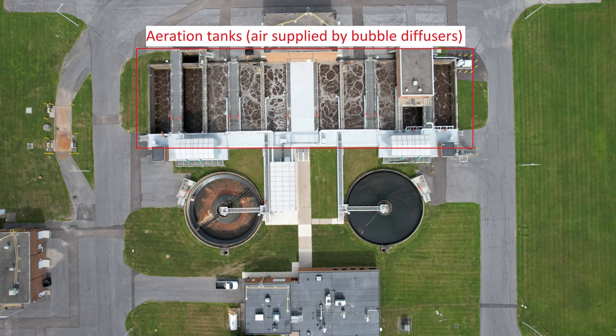This makes sense when you think about it. One of the principal goals of this treatment is to reduce the BOD, or biochemical oxygen demand, of the water. So it makes sense that reducing this demand would involve supplying additional oxygen to the microbes during treatment. We'll talk more about BOD when it's time to discuss the operating parameters. There are a couple of different ways to introduce this oxygen: sometimes mechanical aerators consisting of a motor that drives paddles or blades to froth up the surface are used; otherwise, the plant will install bubble diffusers on the bottom of the tank and blow pressurized air through them.